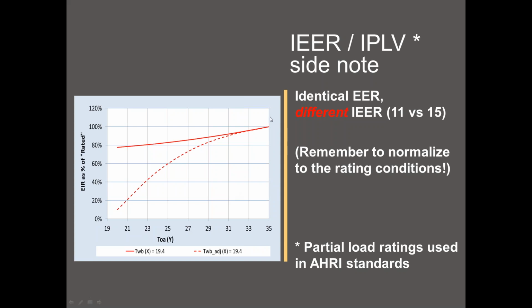You are probably aware, you need to be aware if you're going to be a black belt, that the EER is a single point rating condition and it's the peak summer condition. So it's at 35 Celsius, which is 95 Fahrenheit, and 67 degree wet bulb, 19.4 Celsius, indoor wet bulb condition. It's a single point. So at that single point, you define efficiency. Guess how often the equipment operates at that particular condition?